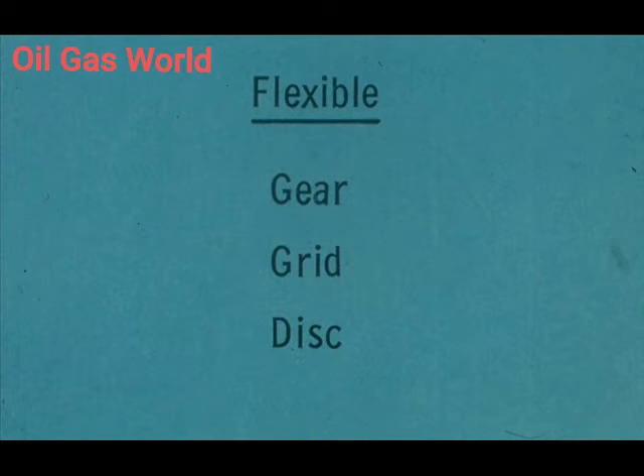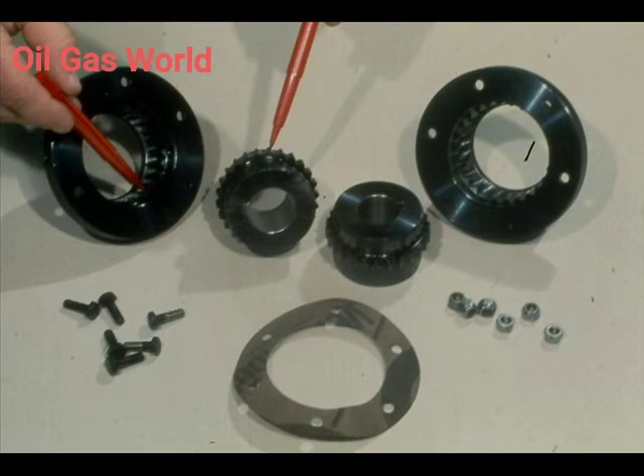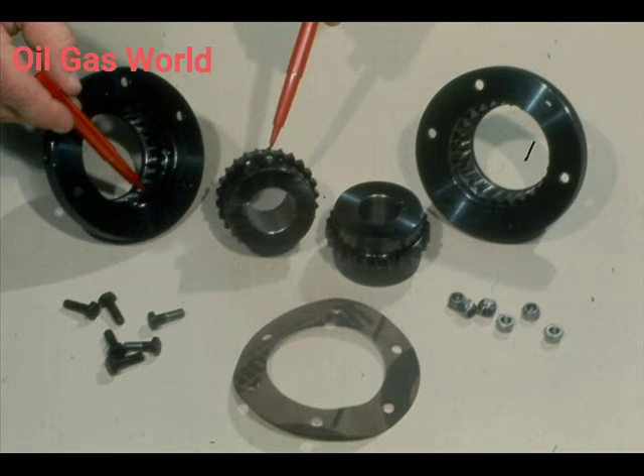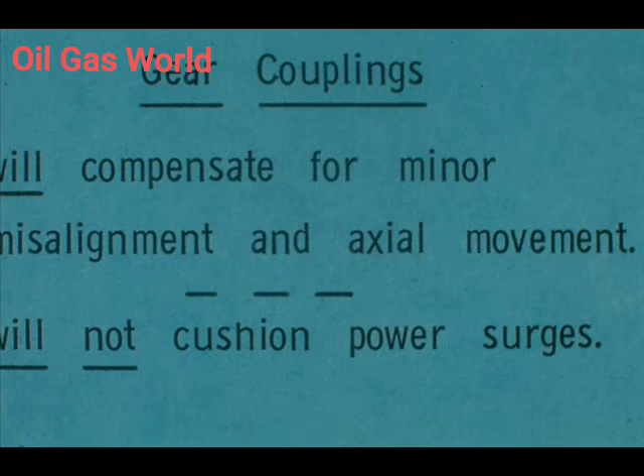Our second class of couplings is flexible. We will cover three types of flexible couplings: the gear, grid, and disc. All of these couplings are more complex than the rigid couplings. This is a gear coupling. It does require lubrication since there is metal-to-metal contact between the gear teeth on the hubs and the teeth in the bells. However, it does compensate for minor misalignment and for some axial movement of the shaft. A disadvantage is that this type of coupling will not cushion power surges or shock.